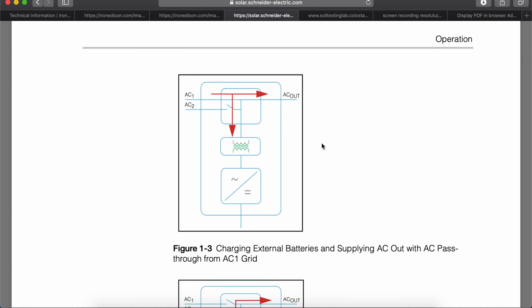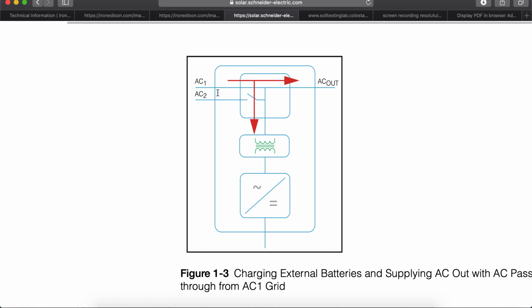In this diagram, we're seeing charging external batteries and supplying the AC out with AC pass-through from AC1 grid. In this diagram, you can see AC1, the grid is coming in, and is simply passing right through the inverter. Like an internal transfer switch, this is all built into the inverter. No need for another secondary external transfer device. Here, we're charging batteries, taking some of that AC power and charging the battery while supplying AC output by passing that grid through the inverter.